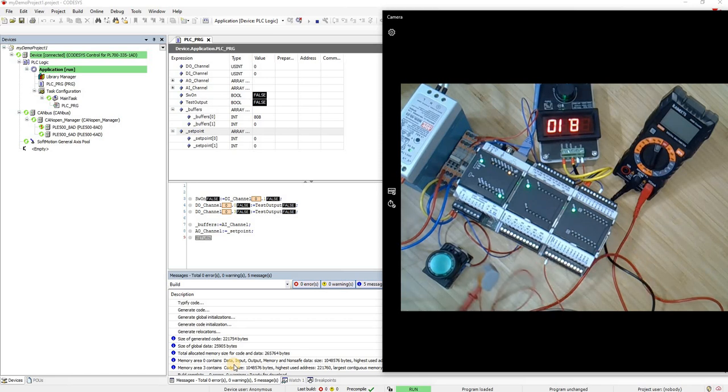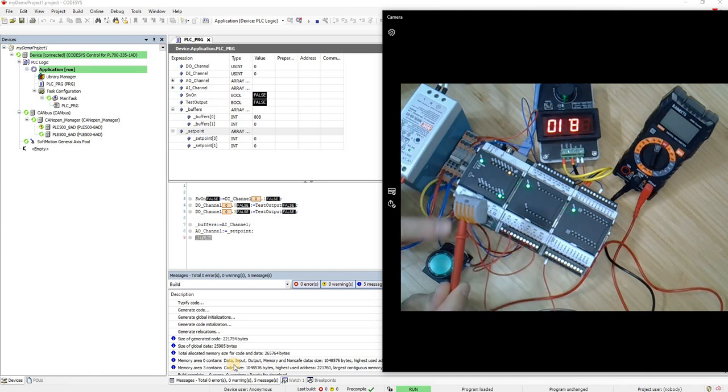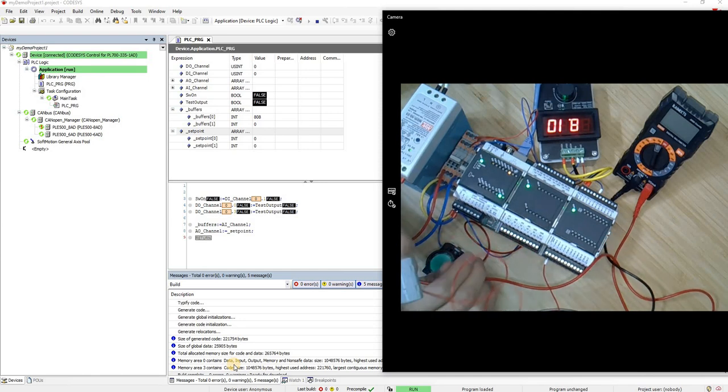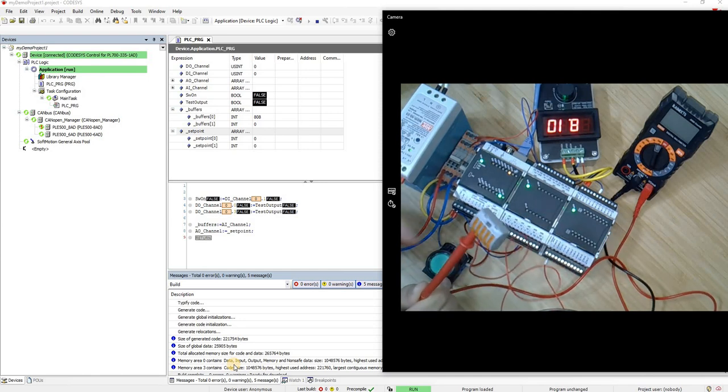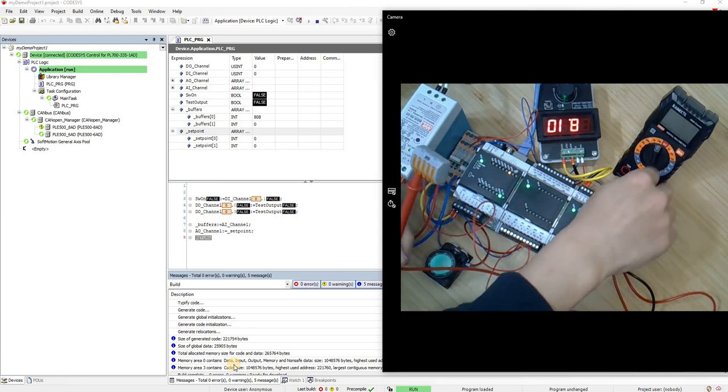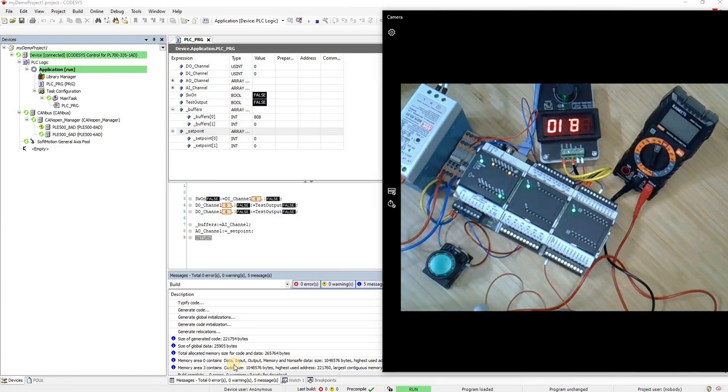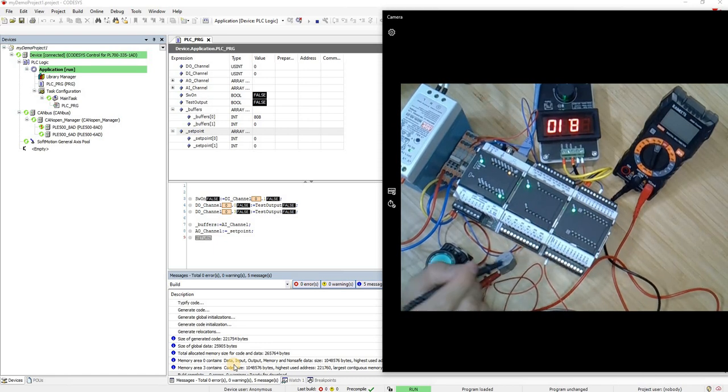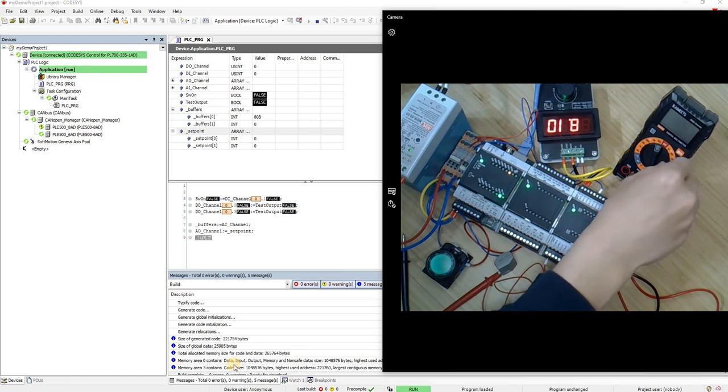I will connect it to a jumper, and then here is the measurement back to the tester. After I turn on and write some value to the analog output, I can measure to check how many milliamperes it is outputting. The first thing we need to do is turn on our tester.